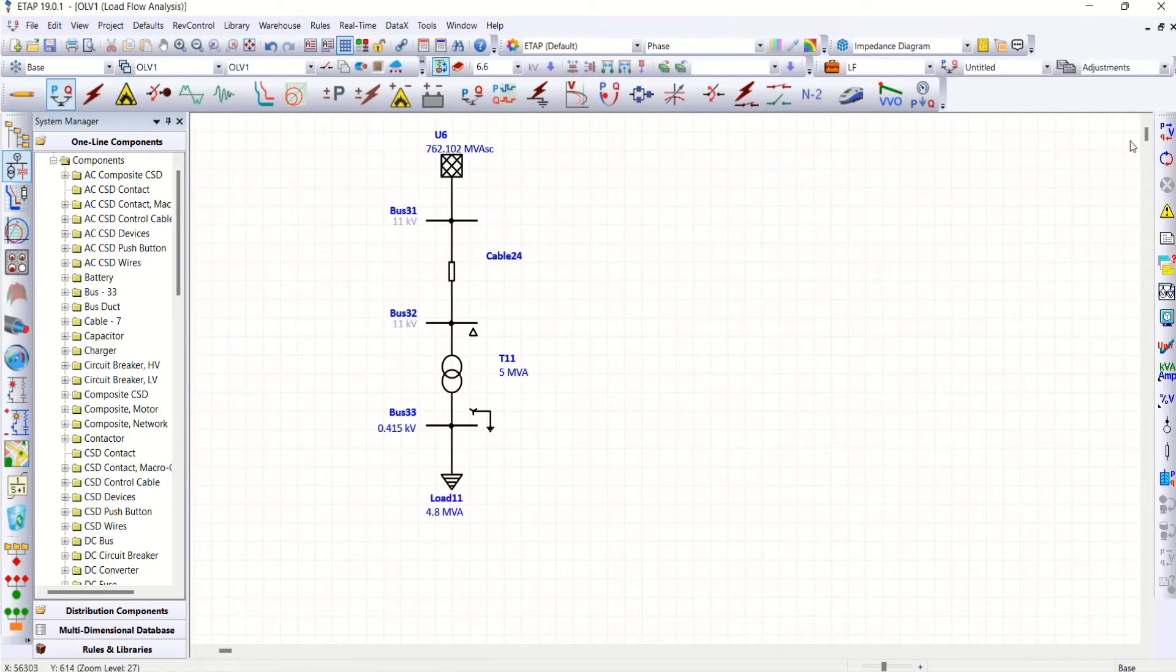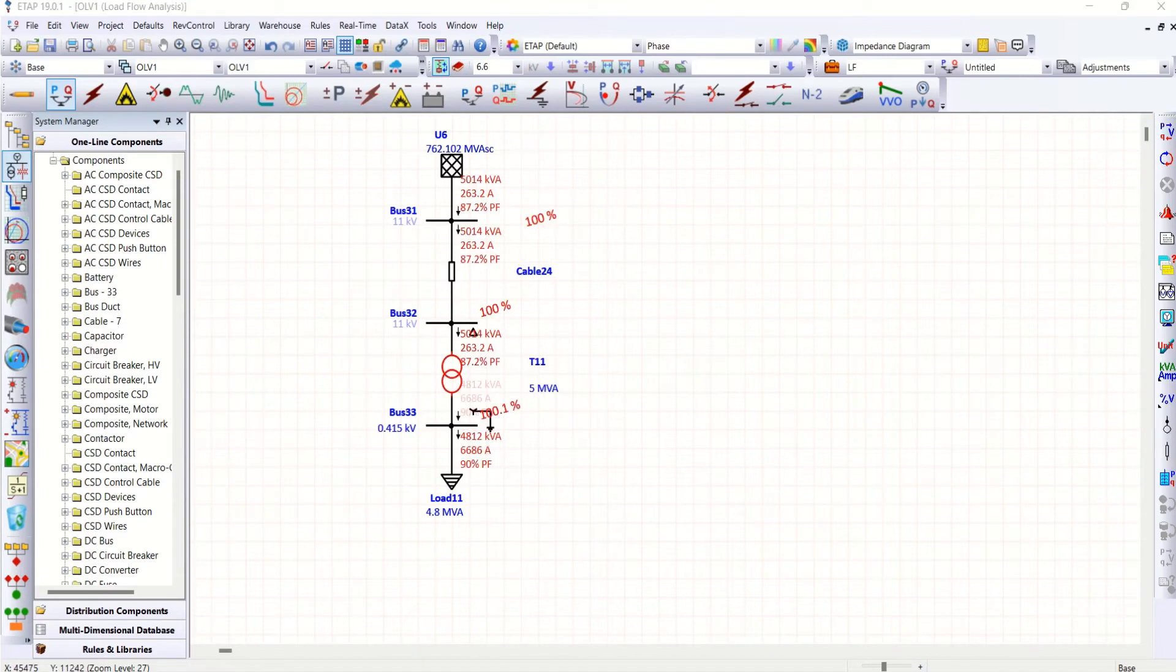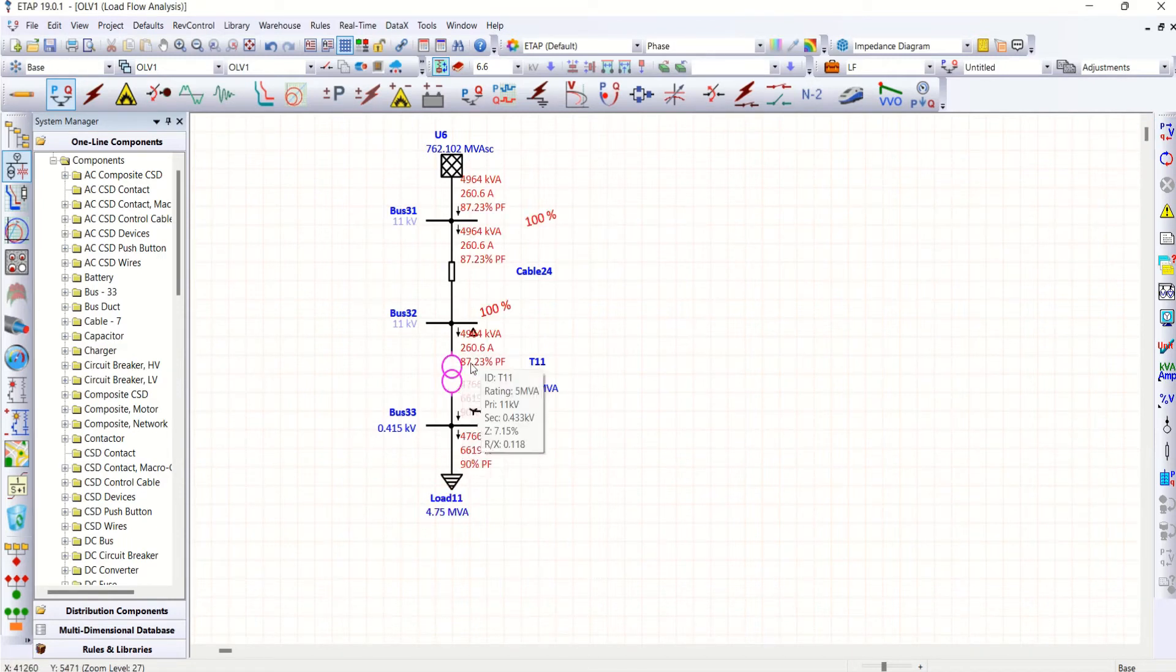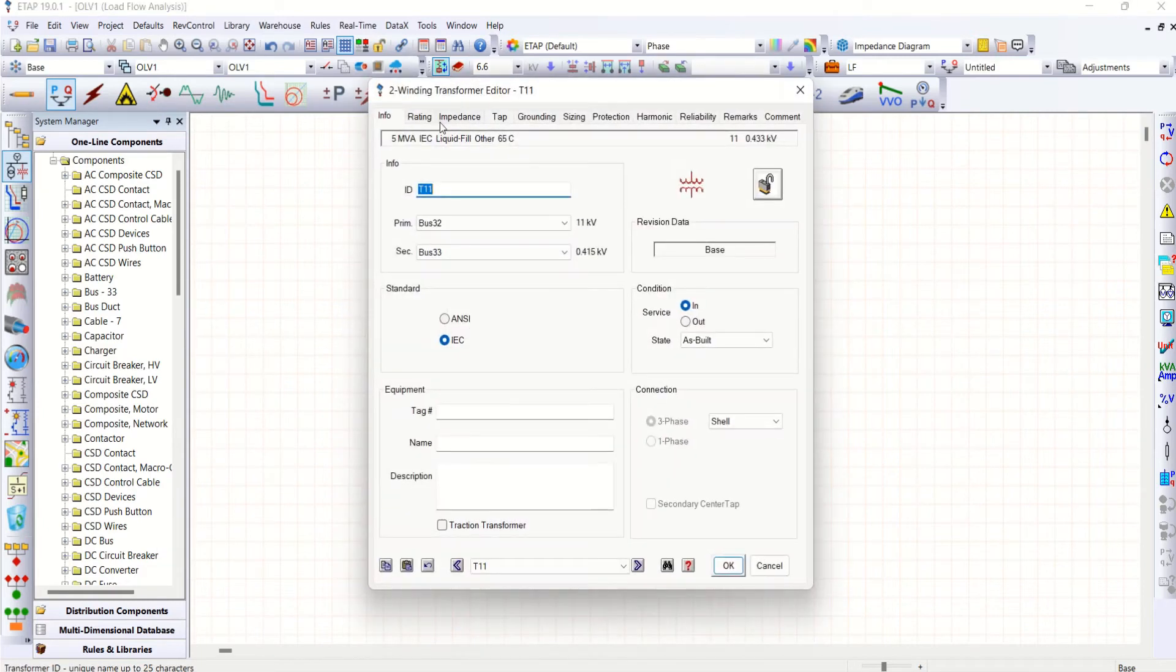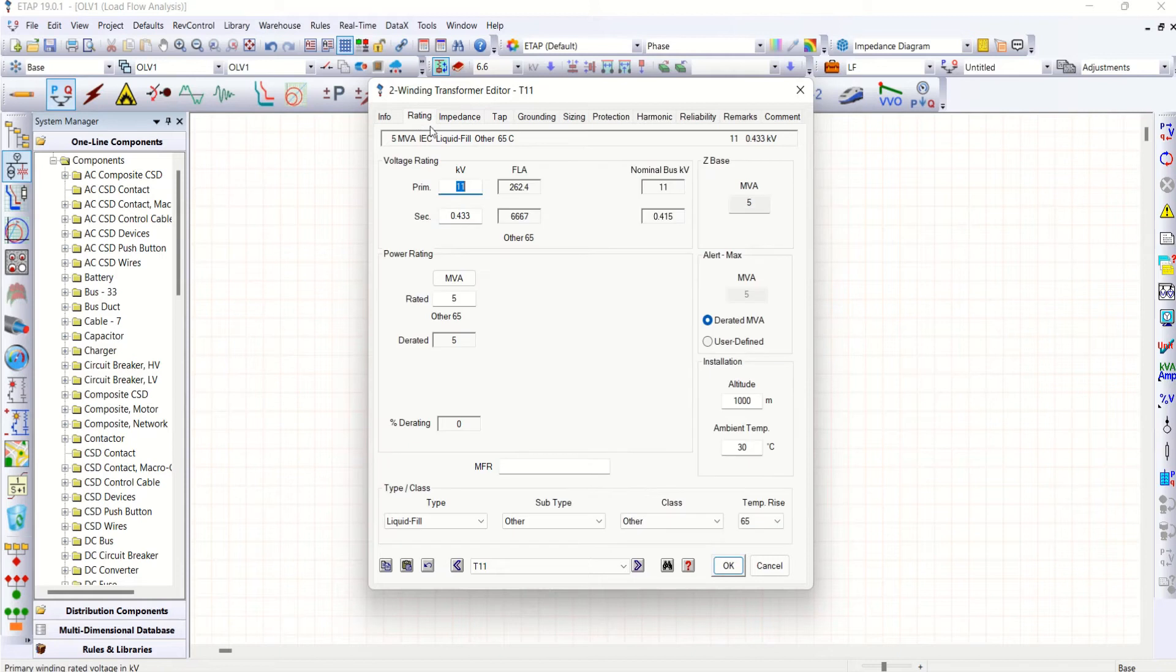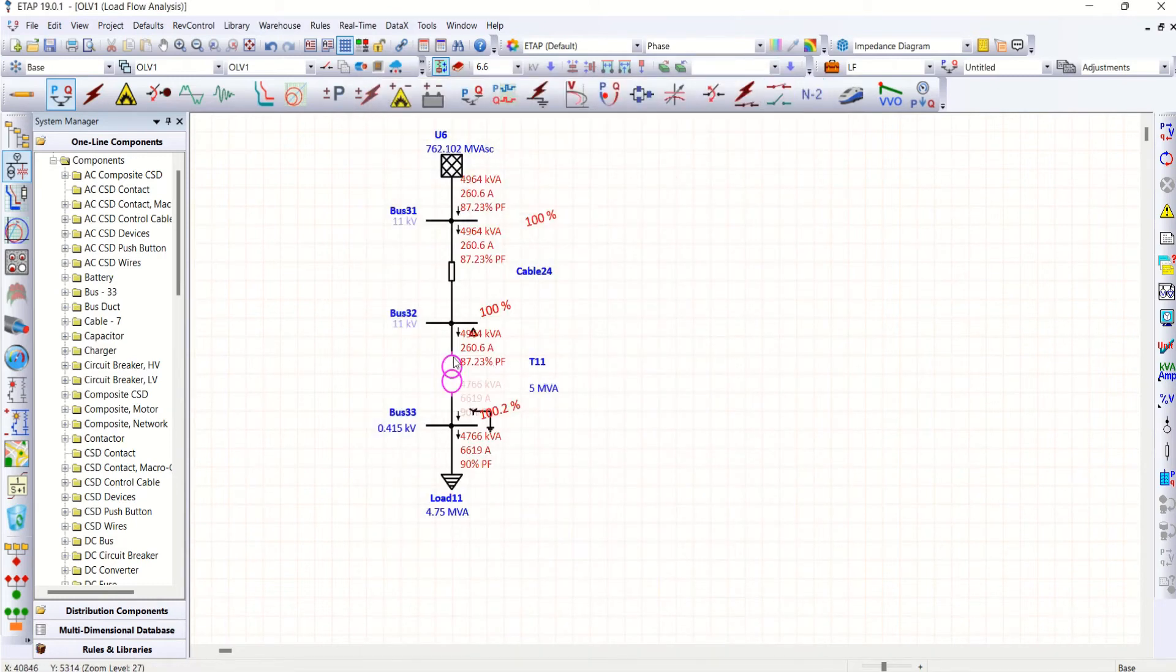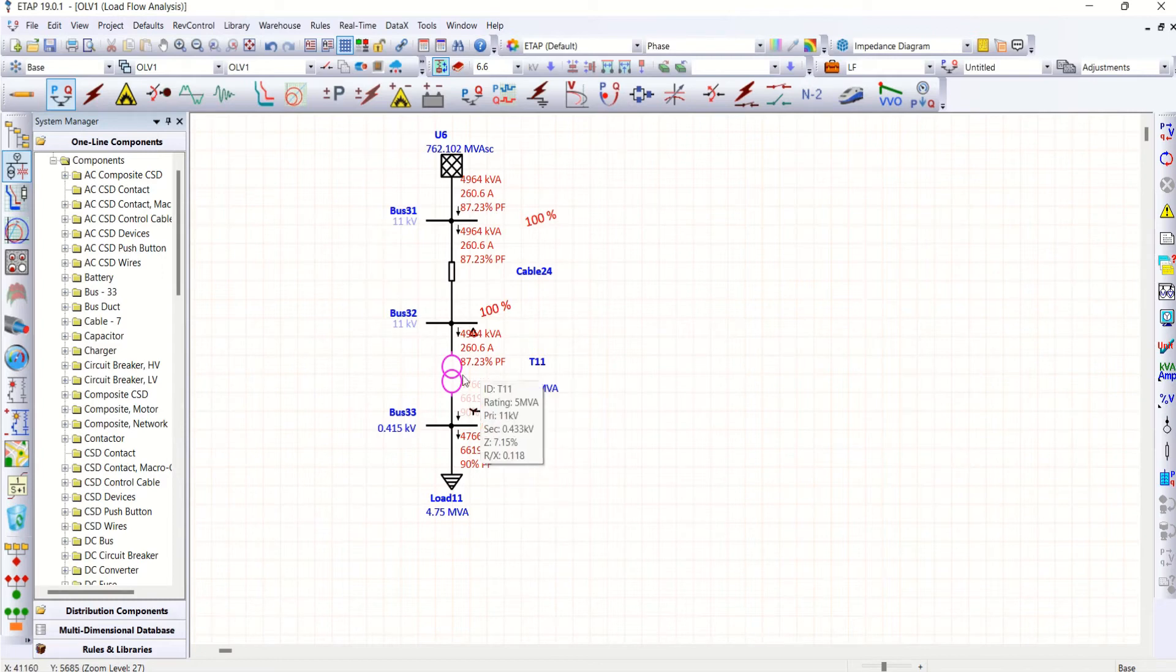First let me check load flow whether it is properly working or not. It is working here. Right, it is marginally close value. Look at the current here 260.6. The transformer rating page you can see 262.4. So close to 100% load. That is what this pink is expressing. So no issues now.